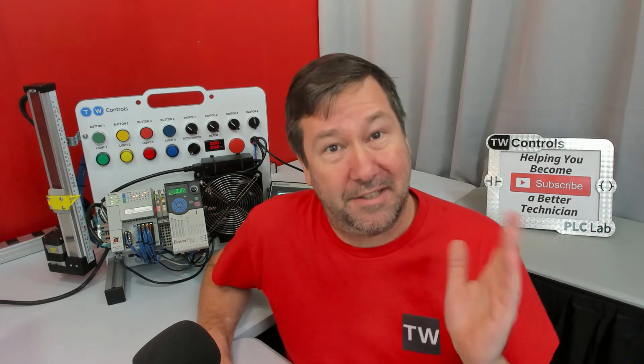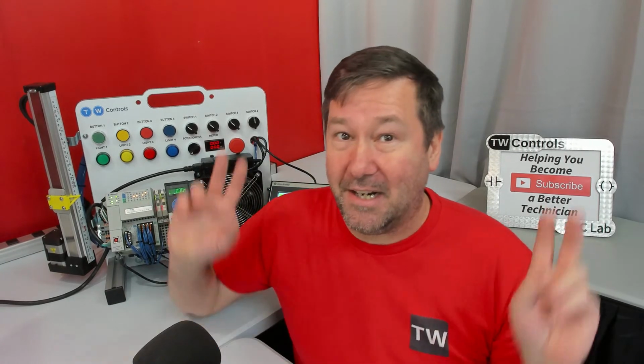Now, the big thing that really confused people on this is how the PLC scans, because we have been taught that PLCs scan their inputs, they run their program, then they update their outputs in that order. And that's what I call the traditional scan cycle. Now, when I say traditional, that doesn't mean old. It just means it's one way the scan works. Also, we call this the synchronous scan.